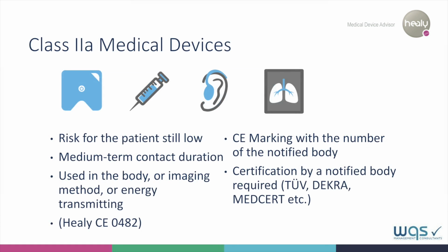Class 2A devices are different. The user risk here is still low, but the duration of the application is medium term, and the application takes place within the body, either by imaging methods or by transferring energy to the body. Other examples are the application of toothpaste in the mouth, or an injection with a drug. This is the class where Healy is to be found. The duration of its application can be determined as medium term, and the application of microcurrent for therapy is transferring energy to the user's body.